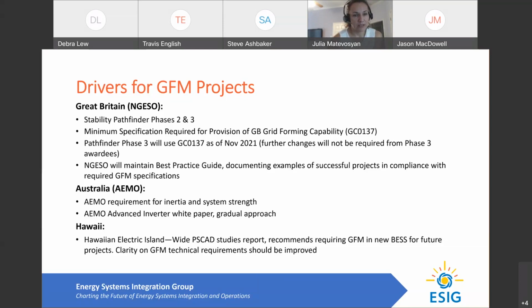In parallel, Great Britain has developed minimal specifications for grid forming capability. This is currently in the stakeholder process for review, and they expect it to be finalized by the end of this year. It's basically a grid code requirement for grid forming capability, not a mandatory requirement, but rather a way to have a market product to incentivize grid forming behavior. Pathfinder is a way to explore the capability of these technologies at a smaller scale before a full-blown market for grid forming service is implemented. For Pathfinder phase 3, the technical specifications for the projects are actually based on this minimal specification I just mentioned.